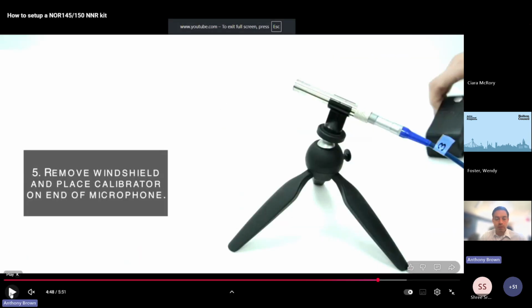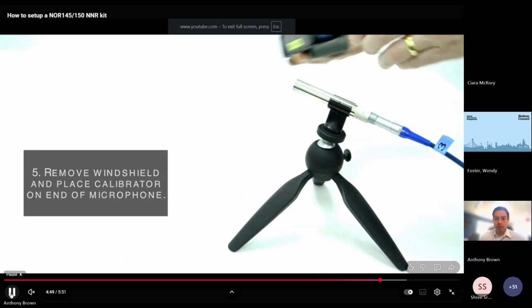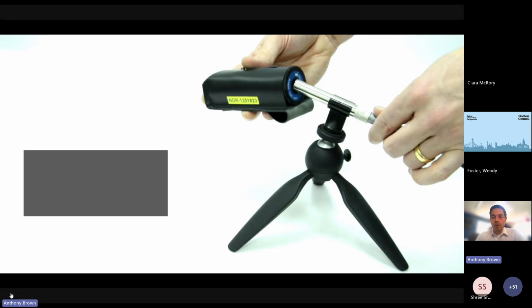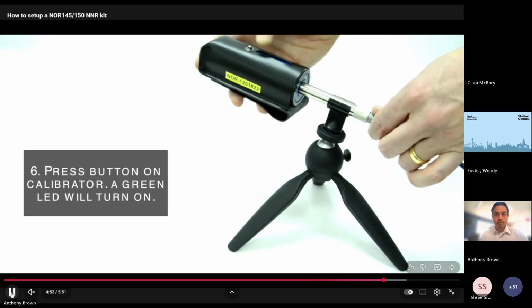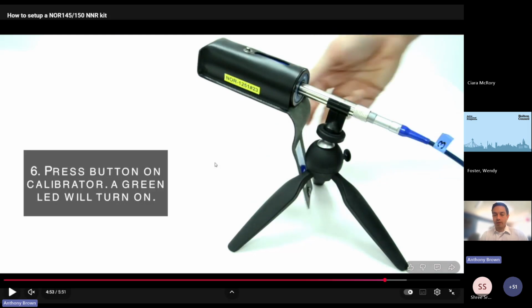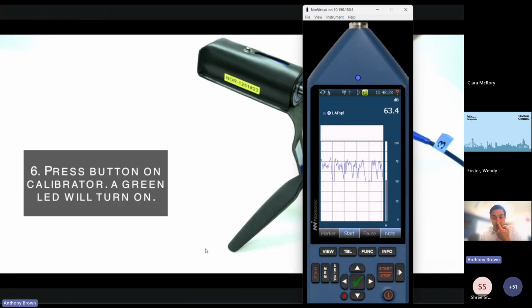So here's your microphone. The calibrator just pushes onto the end of the microphone here. It will go on about a centimeter. It just pushes on, a little snug fit. Then the calibrator will make a beep sound if you press the on button on the calibrator. And on the meter, you're then going to press the cal button. There's a cal button on the keypad here.